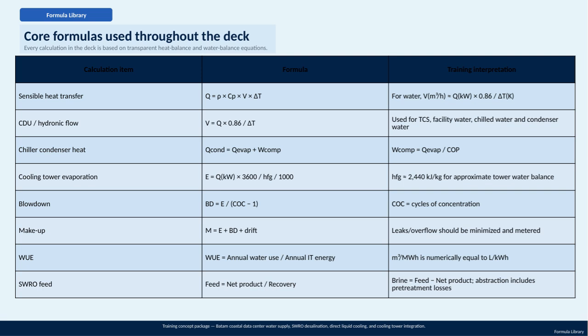Next, we look at the chiller condenser heat equation, which ties together the heat rejected by the chiller condenser, the evaporator, and the compressor power, incorporating the coefficient of performance for realistic efficiency assessments. For cooling towers, evaporation loss is calculated based on the heat load and the latent heat of vaporization, helping us estimate water losses during cooling.